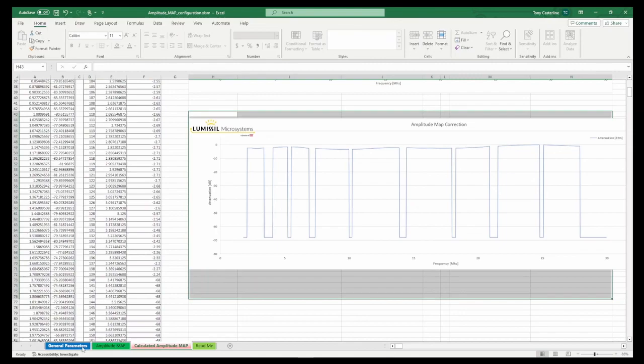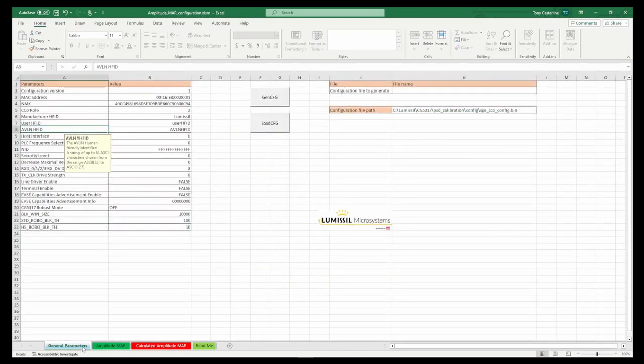We can go back to the General Parameters tab and create a new configuration binary that contains the PSD corrections along with the configuration settings. This binary can be stored in external flash connected directly to the chip, but more commonly, it's stored by the host processor and loaded into the CG5317 via SPI or Ethernet. To make a configuration binary, enter a file name and click the GenConfig button.